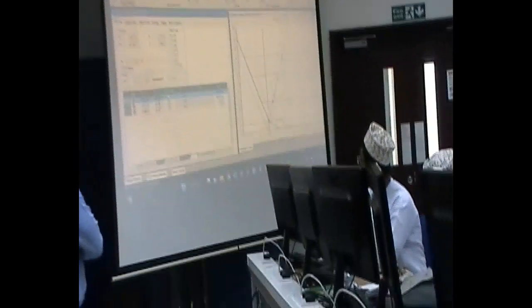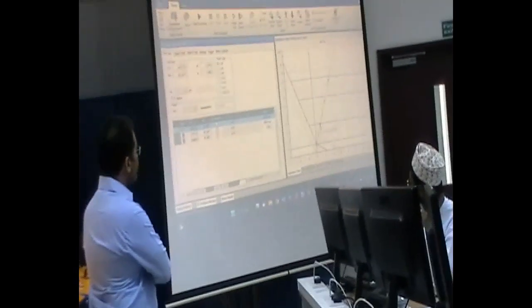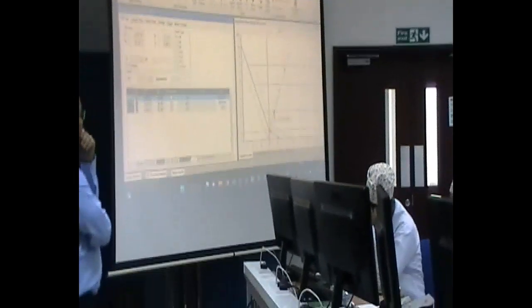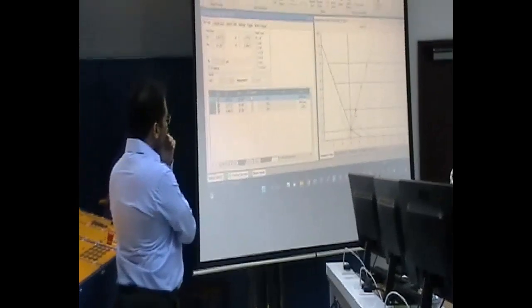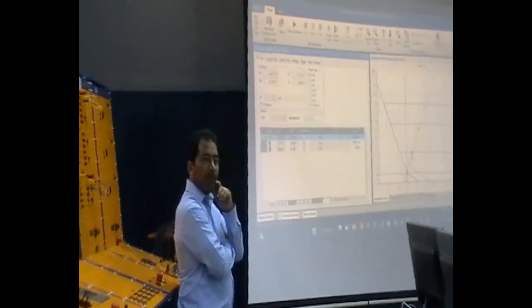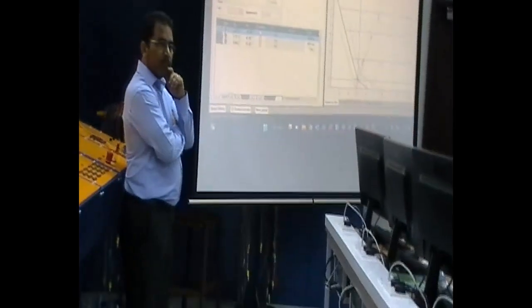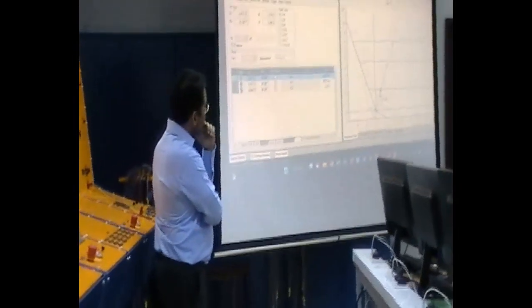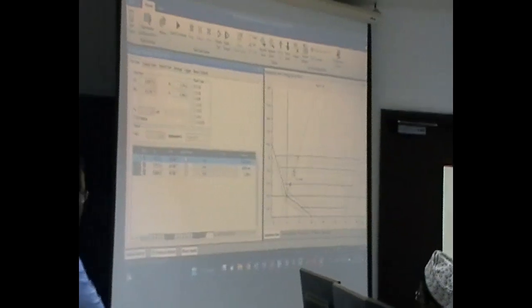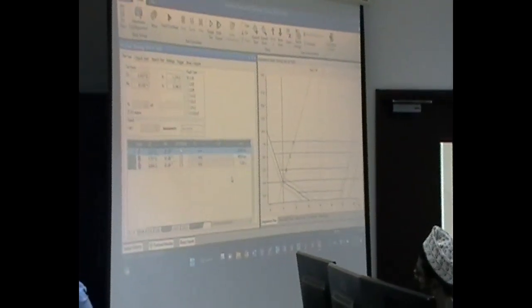Basically what I should be doing is selecting some random point and injecting impedance. This will inject the impedance, whatever I have selected here. Basically it will fix the current and change the voltage based on whatever value I want. I've selected some points here already in zone 1. I have here zone 1, zone 2 and zone 3. I've selected these points for the testing. What I'm expecting is the trip signal.